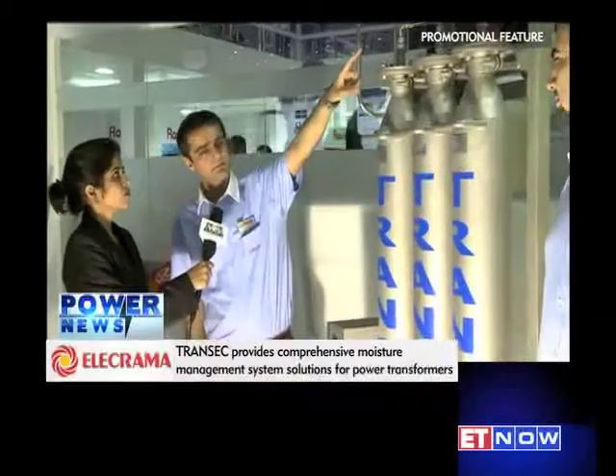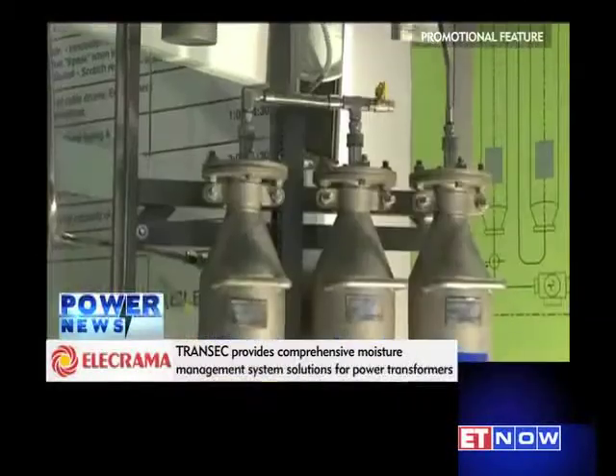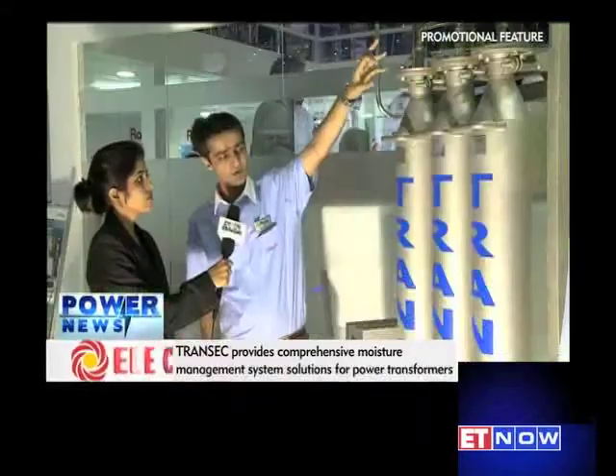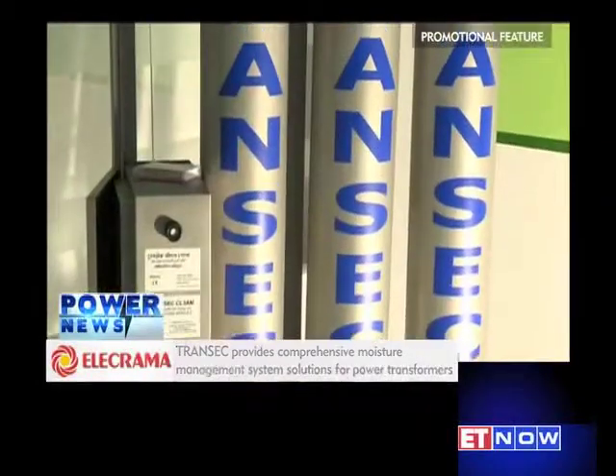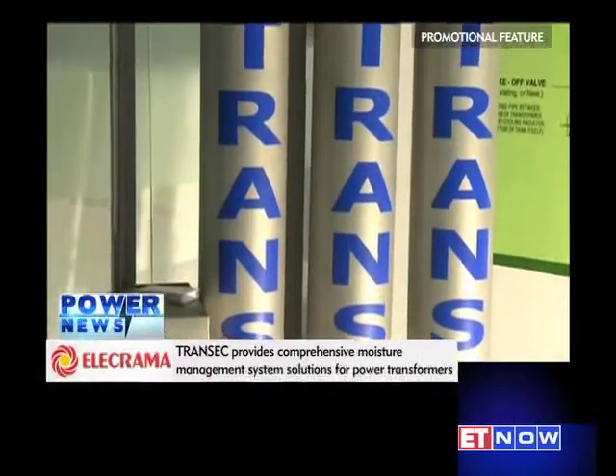Then it passes through cylinders where the moisture from the oil is absorbed. Later there's a deaerator and a particulate filter which filters out fibers in the oil, and then it passes through an output sensor which gives the output ppm and temperature on the monitor. Then it's pumped back into the transformer.